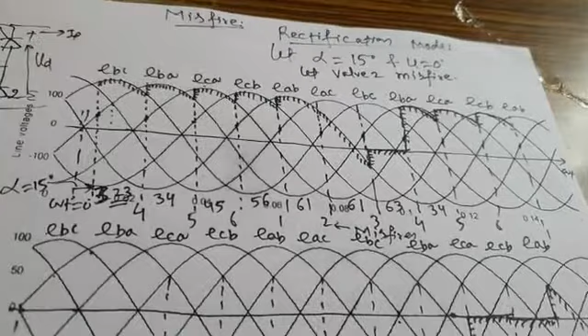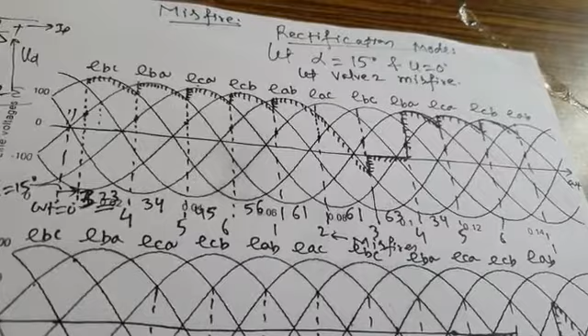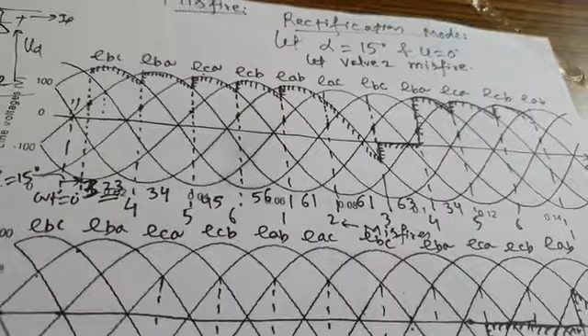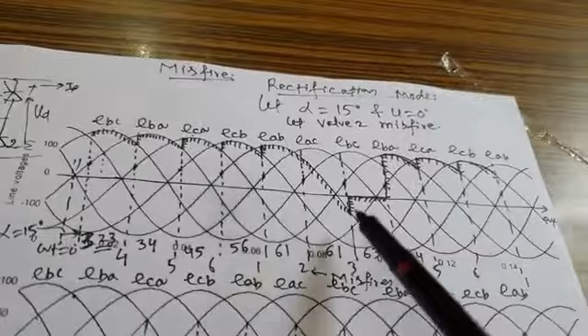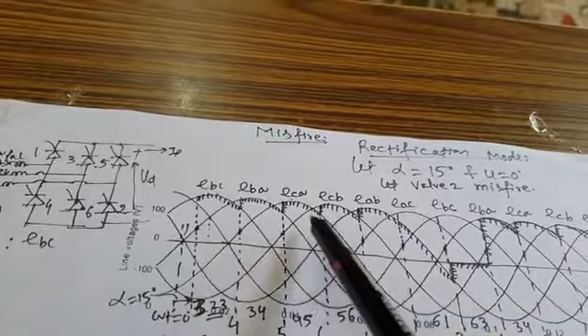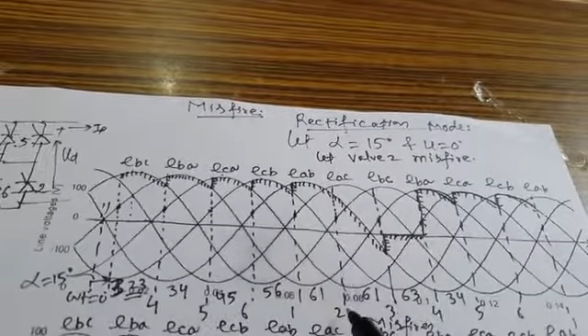That's another mal operation. Misfire is a condition in which a thyristor is forward biased, it is given a firing pulse, but it fails to fire. It fails to go into conduction during its scheduled conduction period. And because of that, as you have seen in both rectification mode as well as inversion mode of operation, your load voltage changes. For example, in rectification mode, your load voltage under normal circumstances for alpha equal to 15 degrees should have followed this pattern. But as soon as misfire of valve 2 occurs, your load voltage pattern changes. For a small period, it becomes negative, and for a 60-degree interval, it becomes positive, and then it resumes its normal operation.